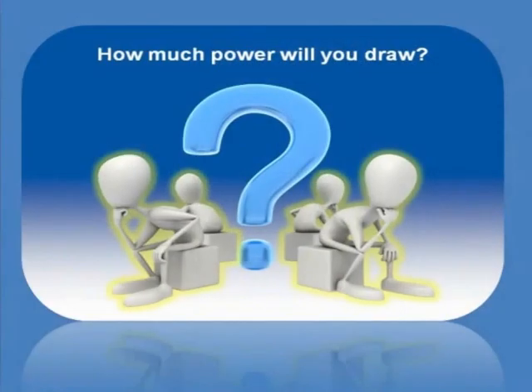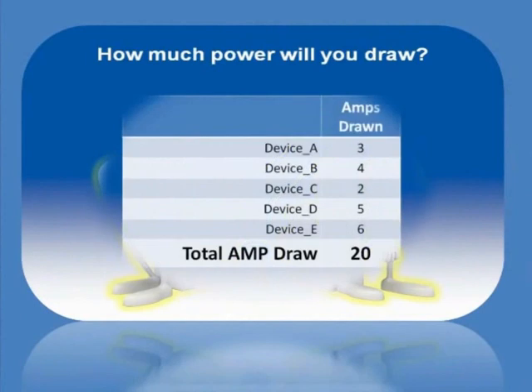The answer to the question of how much power will your current servers and storage devices draw is to add up the amp draw on all equipment that will be plugged into the PDU. You then have the total amp draw for that PDU. The amp draw information can be gathered several ways.